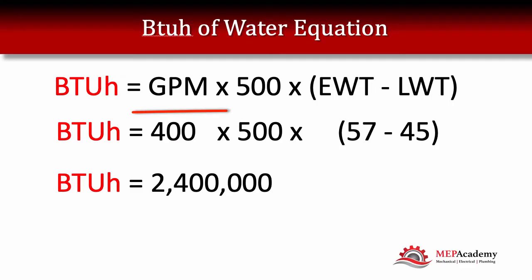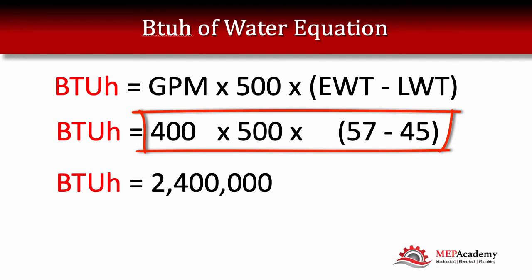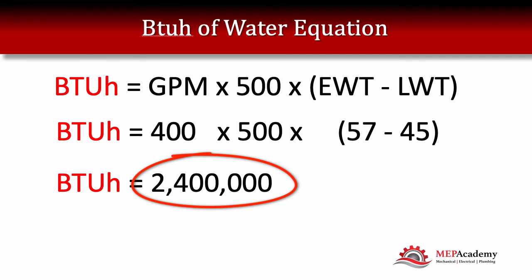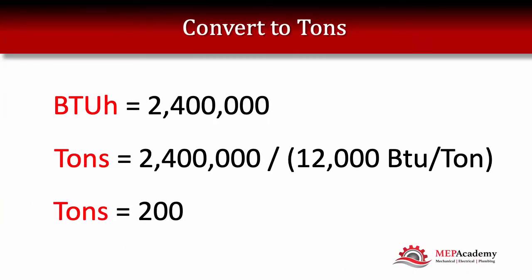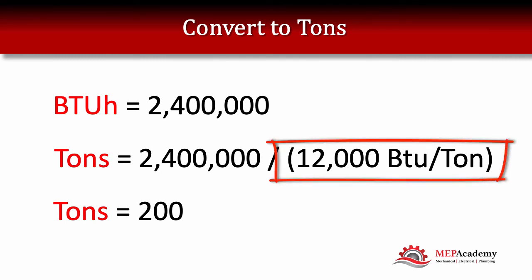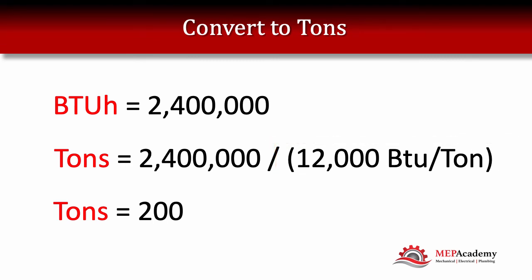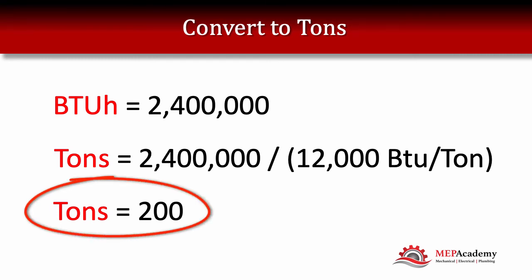Multiplying it out: 400 times 500 times 12 gives you 2,400,000 BTUs per hour. Since there are 12,000 BTUs in each ton, you take 2,400,000 and divide by 12,000 to get the quantity of tons — so that is a 200-ton chiller. That chiller is rated for 200 tons.